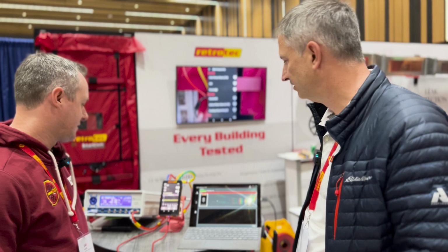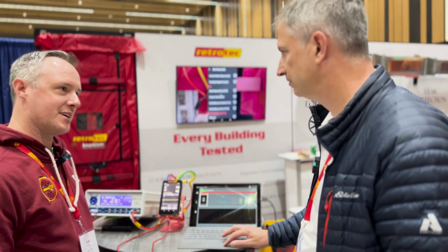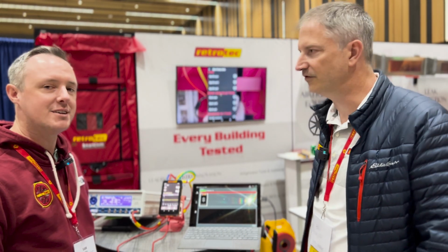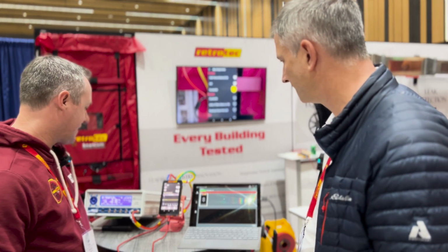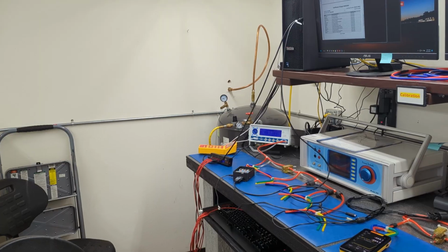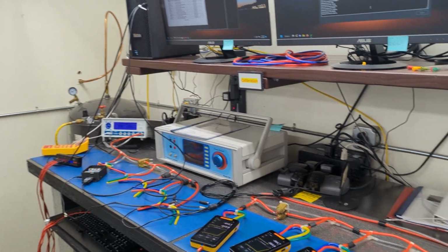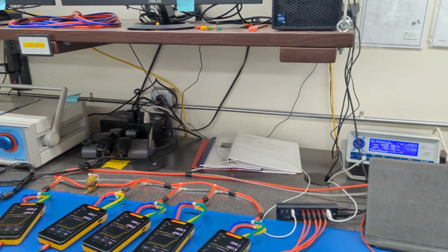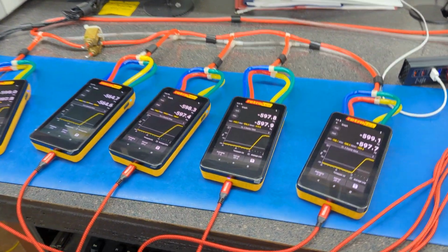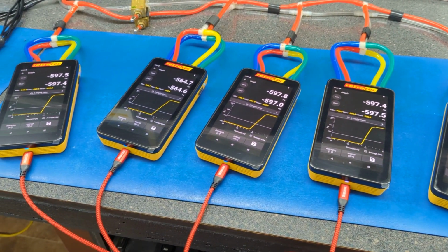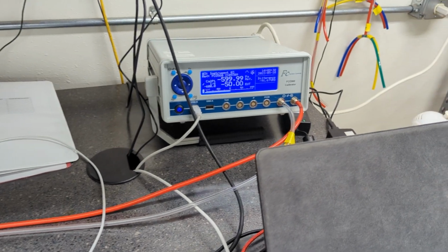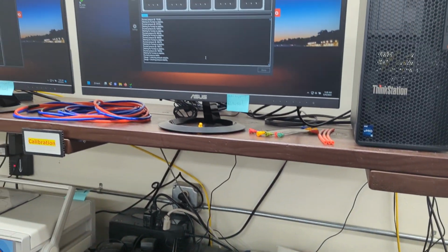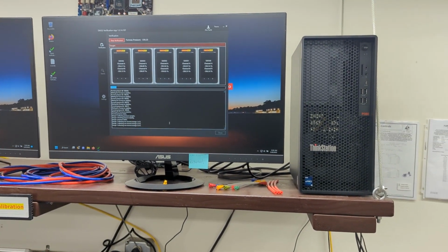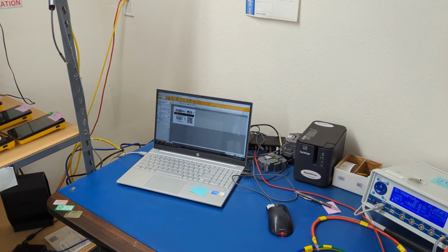Cool. Yeah. Well, it's great that this is actually something we can travel with now. Yeah, definitely. It's a great new service we can offer. Yeah, exactly. Cool. So back at the lab, we have several of these? How many can we hook up to one device? Sure, at the lab we typically would do maybe 5 gauges at a time for each of the furnaces, and so it takes a little bit. It takes 45 minutes to do 5 gauges or 20 minutes to do a single gauge on one furnace, and we have 2 furnaces for redundancy, and then we also have another furnace that we use for our 30-inch pressure sensors as well.